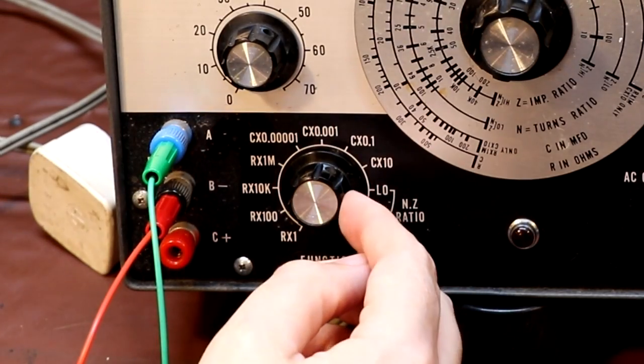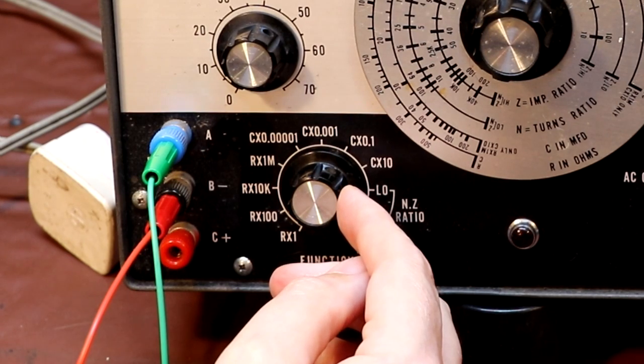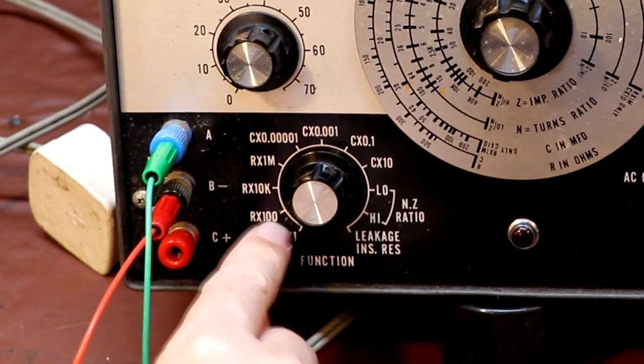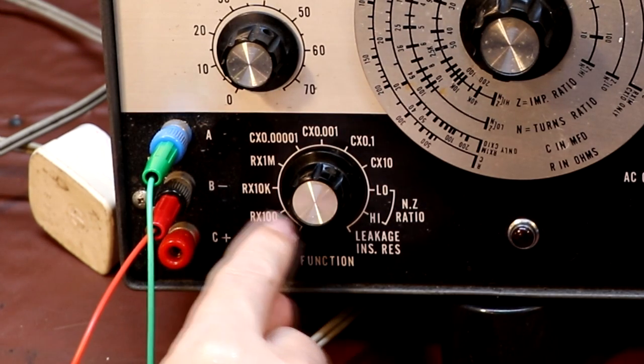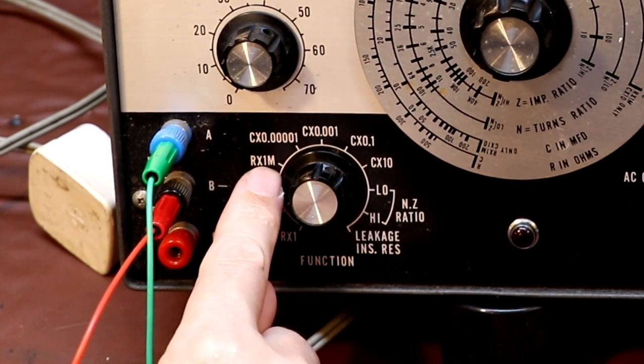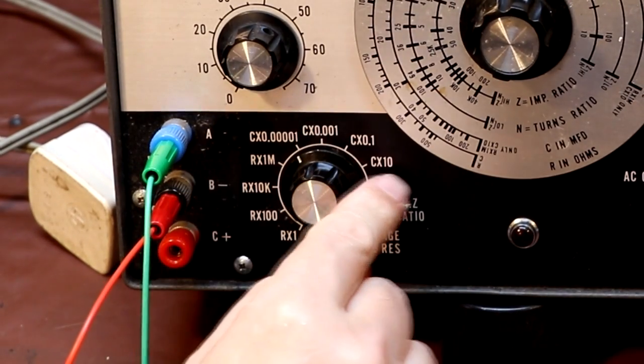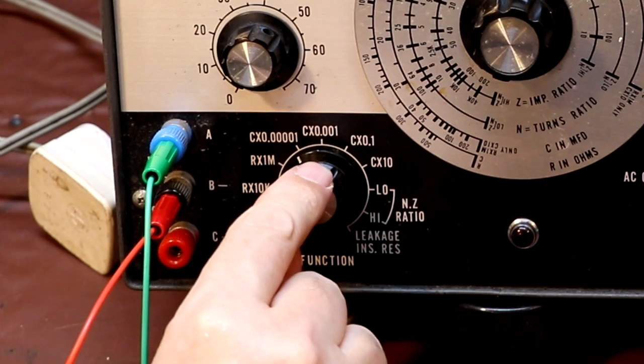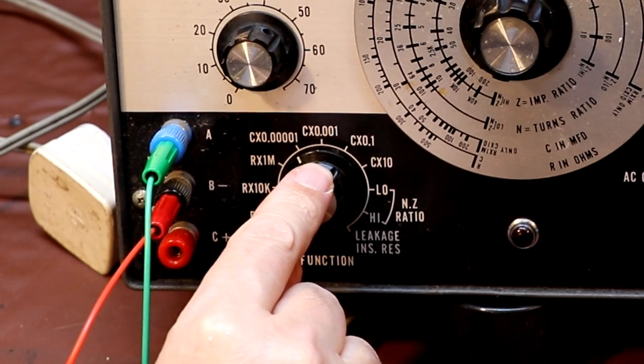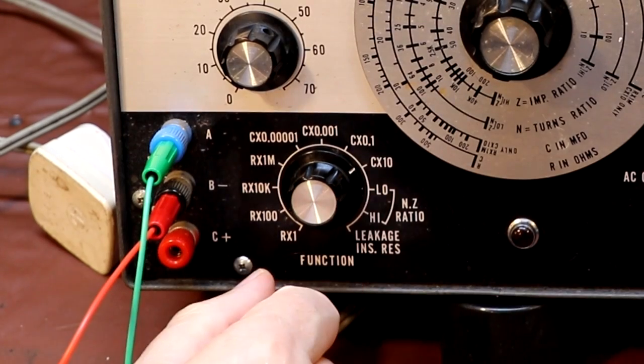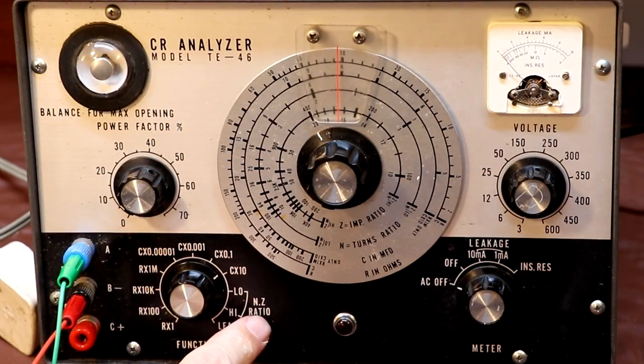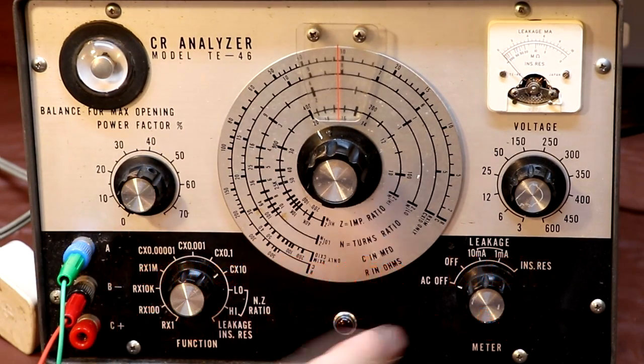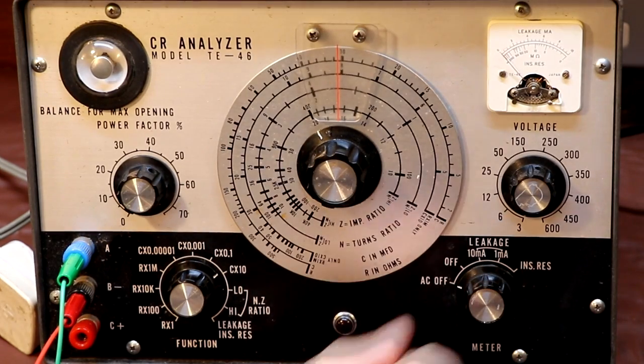So we've got a function select switch here at the bottom left of the instrument, and what you can select from, we've actually got four ranges of resistance values here, which go from about 2 ohms up to 200 megohms. We've also got 4 decades of capacitance ranges, and those range from about 10 picofarads all the way up to 2000 microfarads. So this capacitor resistance analyzer does also have some additional functions, and those include it can actually measure leakage within capacitors, it can measure dissipation factor, and it can also measure insulation resistance using this control over here.